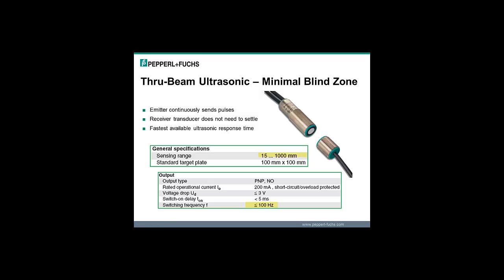Now with the Thru-Beam model, we were discussing a diffused model before, there is a very minimal blind zone because now you have a dedicated emitter and a dedicated receiver. The emitter is constantly sending out, and the receiver is constantly listening. That allows for a very small, if non-existent, deadband. So you can see here, you've got a 1 meter, 1,000 millimeter sensing range, but you can put these as close as 15 millimeters apart and still have a nice strong signal between them with no issues as far as ringing and multiple reflections.